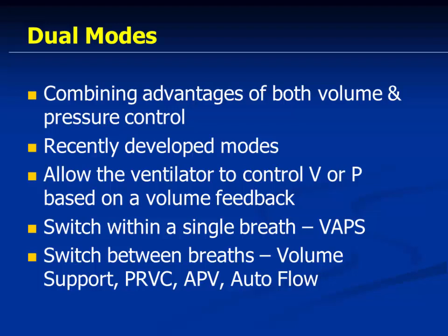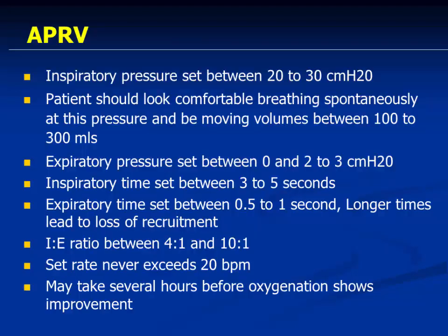So they are mainly microprocessor type of ventilators, and they started coming in the market in the late 80s when ventilation changed from solid state ventilators to microprocessor based ventilators. Because in solid state, combining two modes was not possible. It became possible because of the microprocessor based technology.